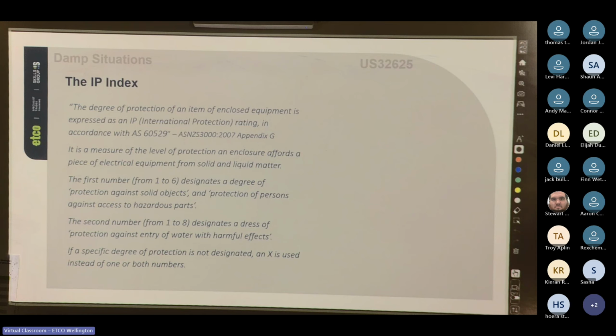So when you see an X on the IP code, it doesn't mean zero protection. It just means that part of the test wasn't carried out or declared. So it very well may meet one of the numbers, but they either didn't test it or they didn't declare it. For example, IPX4 means we don't know about solids, but it is splash proof against water. That's why in bathrooms we often see IPX4. We only care about water and not dust in the bathroom. Does that make sense?